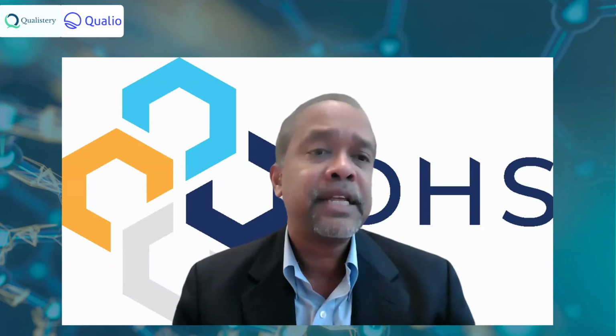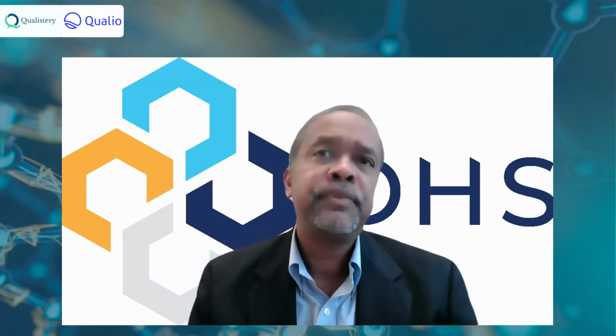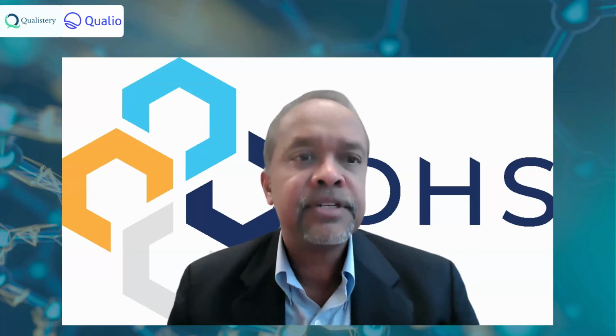You have to be in compliance with the AI standard, but your starting point would be intended use. How do you intend to use the device? If the device is going to use AI to make changes in the therapy you're getting with, for example, a pain management implant device, right? Then validation is much stronger. Risk analysis is very heavy. So you identify all the controls that need to be put in place and implement. So in context of a US submission we were making, how to handle AI responsibly, that's how I would do it. Perfect. Thank you so much.